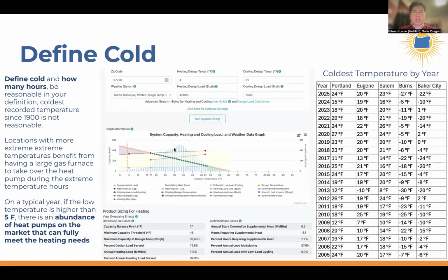So, this example here is in Burns, Oregon, and Burns gets significantly colder than the cities that are west of the Willamette Valley. They actually get days when it's, you know, minus Fahrenheit, so very, very cold. And so you can see here that there's a significant number of these blue bars that are in this purple area. And so this would be a location where a dual fuel heat pump would have greater benefits, because during these hours the heat pump is not able to keep up, and so then a dual fuel heat pump with that much higher output could then come online and be able to keep the house comfortable when it's 5 or 10 degrees outside.